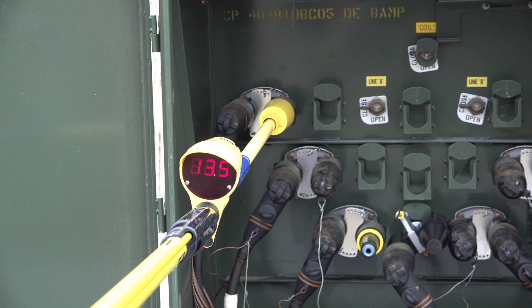So by installing a 0 ohm extension to the VD1000, we learned two things. Number one, by installing the 0 ohm extension, the reading is much more accurate than not having the extension on because the meter housing is much closer to a ground plane. And more importantly, you're working in a much safer environment now because the meter housing is further away from the ground plane. The probe and the 0 ohm extension working in conjunction can be viewed as a form of PPE. In other words, by achieving a much more accurate reading, you've also achieved a much safer environment.